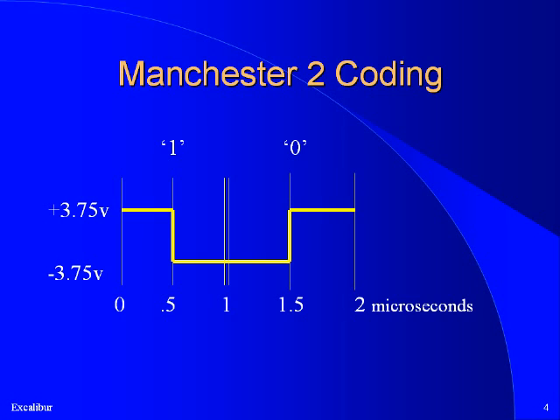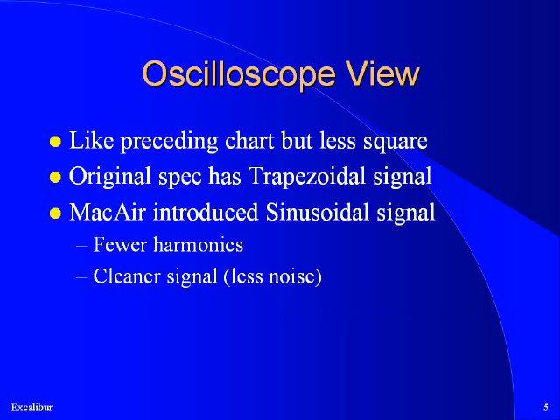And remains there for the remainder of the bit time. Sync signals look similar except that the midpoint comes after one and a half microseconds rather than after half a microsecond. Looking at a 1553 bus using an oscilloscope will show signals that behave pretty much as described. The one difference is that in the real world there are no right angles — the transition is more gradual. A sinusoidal wave has a very gradual curve from one value to the next, whereas a trapezoidal curve has some angles, but not 90-degree angles. Even devices designed to transmit and accept trapezoidal signals will be able to properly interpret sinusoidal signals, so it is possible to use a mix of remote terminals on an aircraft as long as the bus controller transmits sinusoidal signals.